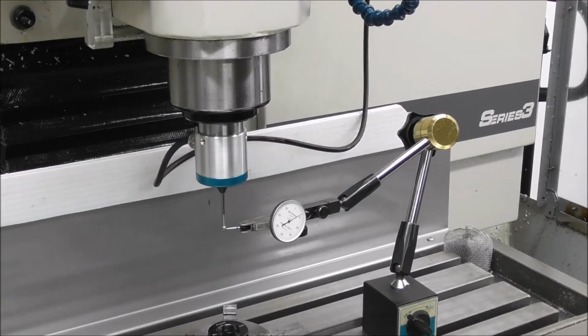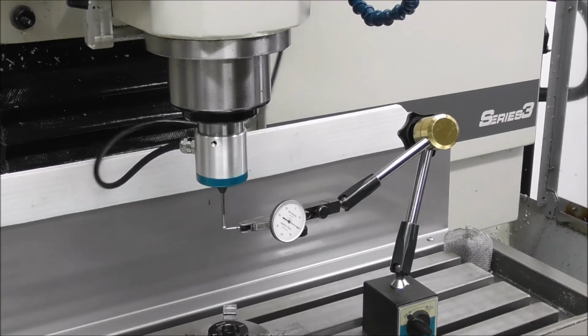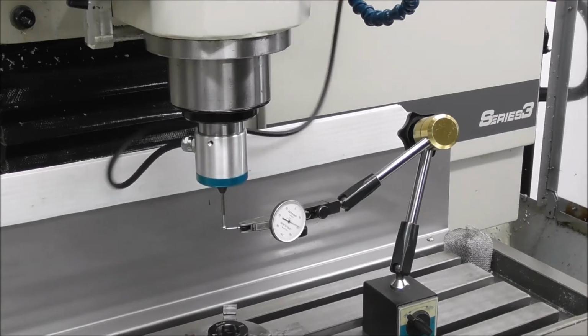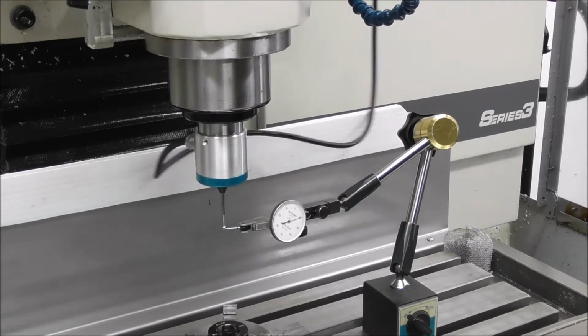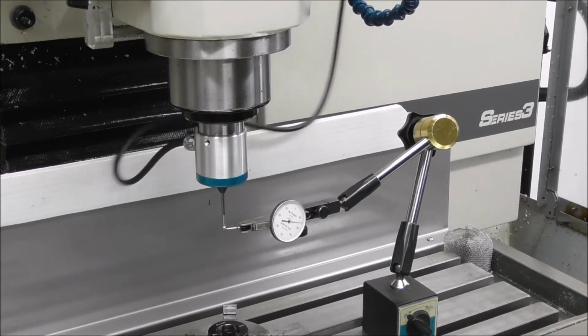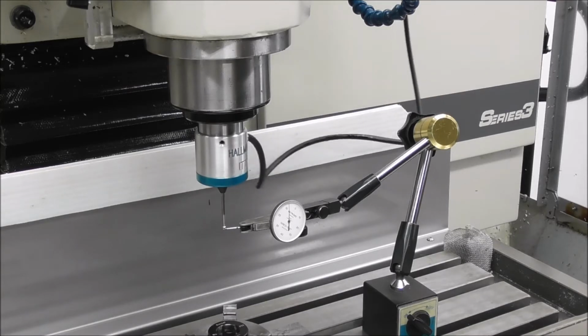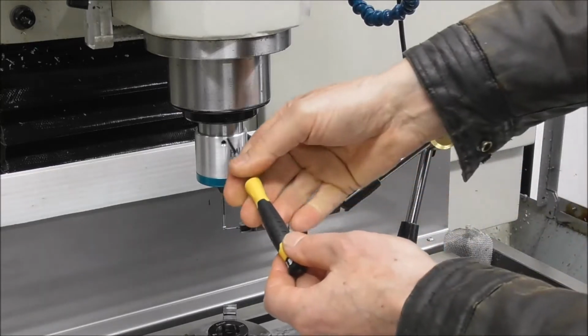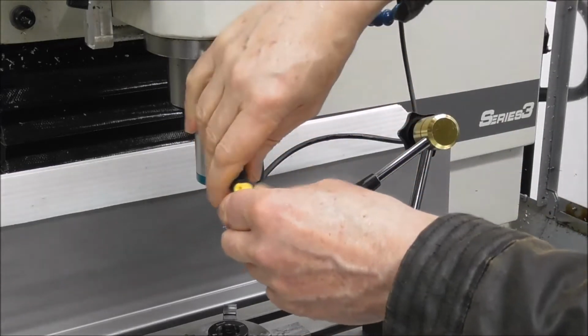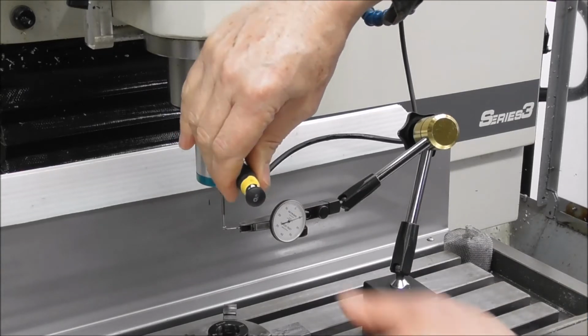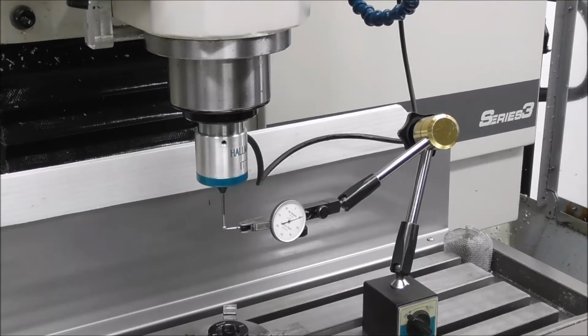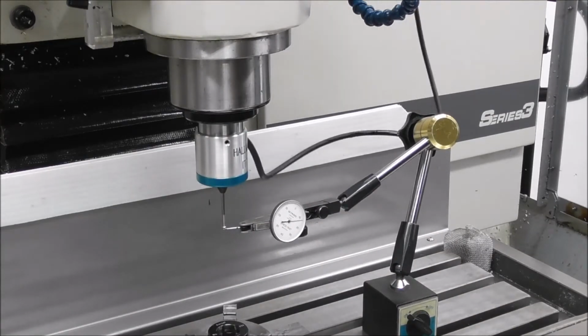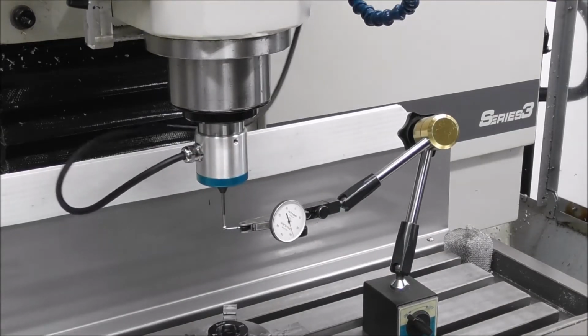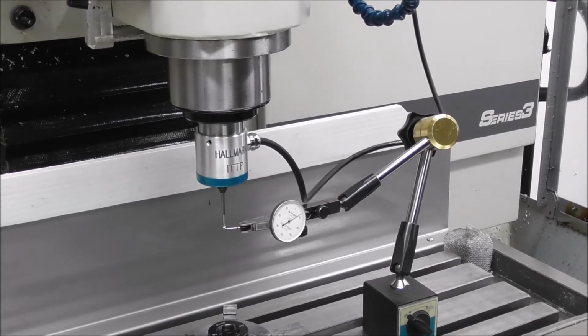Now we'll rotate it and see the extent of the run out. So we are approximately 2/3 of a revolution of the dial, quite a long way out. Okay, so let's go to our most anti-clockwise position, which is about there, and we will adjust screwing in. You see that okay? About half that amount, and then back that grub screw off again. We don't want it to interfere with the adjustment. Now let's see how far out we are. We're now within approximately 0.2.